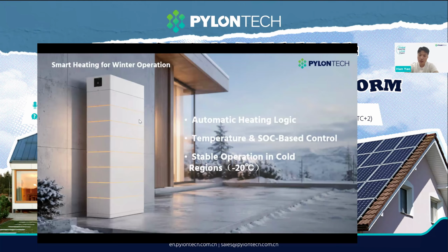And cold weather is a real challenge for batteries, and this is where Pylontech brings a clear new value. This system includes automatic heating logic, temperature and SOC-based control, and support for operation in cold regions down to minus 20 degrees Celsius. The users don't need to manage every heating event. The system checks the battery condition and starts heating when it is needed. This helps protect charging performance and gives installers a stronger solution for northern and mountain regions.